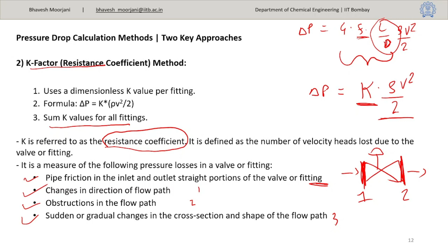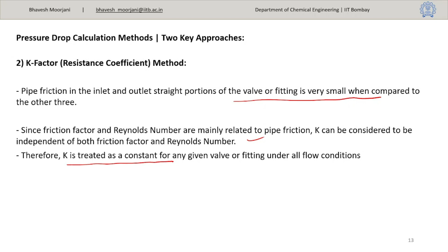So that's why we could make the modification, because L by D equivalent will remain the same for a particular fitting, right? Let's say for a 90 degree elbow we kept L by D as 30, then for that fitting it will remain the same, but the value of f will change. But now we are assuming that at the inlet and outlet of the portion of the valve or any fitting, the friction losses are very small, so we can assume it to be constant. So that's why 4f times L by D can be converted to K, right? So that's why K is treated as a constant for any given fitting under all flow conditions. Okay, so that is one thing to understand.